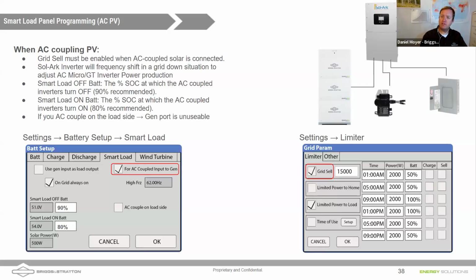And so, Nathan, you had mentioned that the Sol-Ark is grid forming. Does it adjust the grid? Does it form maybe a different frequency? I'm kind of leading you here with this question. Yeah, exactly. It's a great question. An AC coupled array composed of IQ 7 pluses, like we were looking at earlier, is going to produce as much AC power as possible and try to feed it back to the grid. Well, if the Sol-Ark has formed the grid, then those microinverters might be producing more power than the home is consuming. They might be producing more power than the batteries want. And so one of the things that the Sol-Ark can do is turn off the AC microinverters and adjust their output rate by adjusting the frequency.